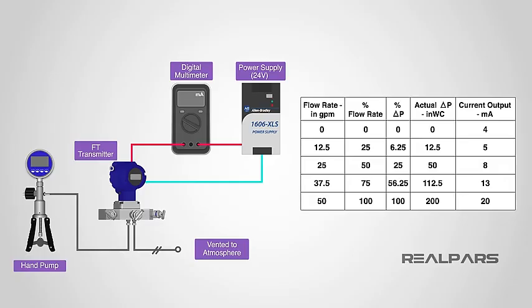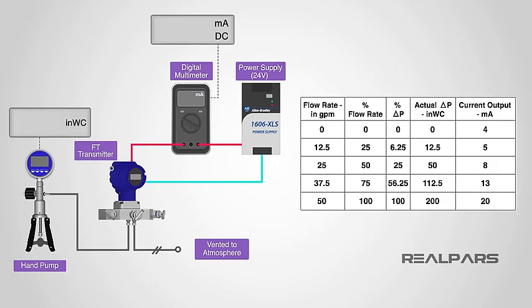From the table, we can see that if we set the hand pump input pressure to 50 inches of water column, our multimeter should read 8 milliamps. Okay, now we've seen how the calibration table will work for us. We've got the transmitter all set up. Let's do some testing. First of all, we're going to check to see if the transmitter needs to be adjusted.